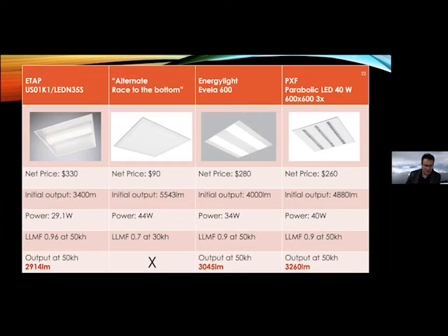So in the end of the lifetime, at 50,000 hours, they will still be producing around 2.8 up to 3.2 kilolumen of flux. Okay, so that's what you want to see. The second product, unfortunately, has to be replaced before we can evaluate its output at 50,000 hours, because it's got aging like no other.